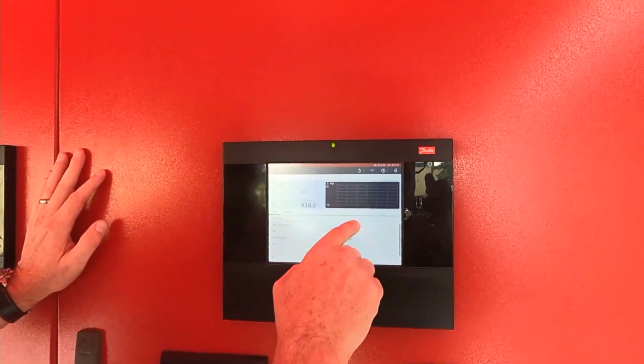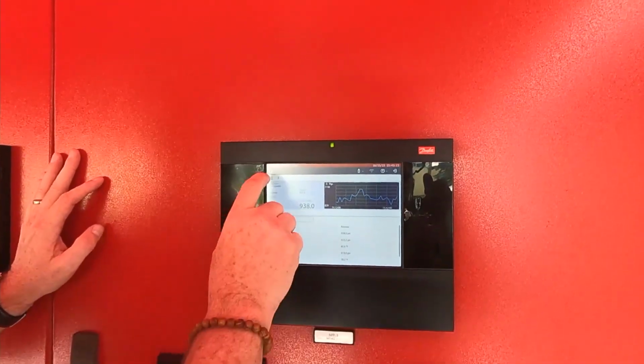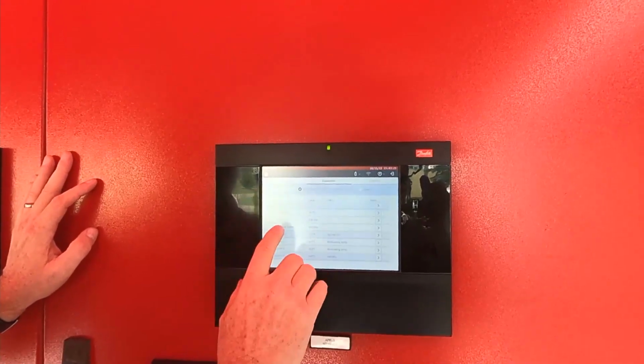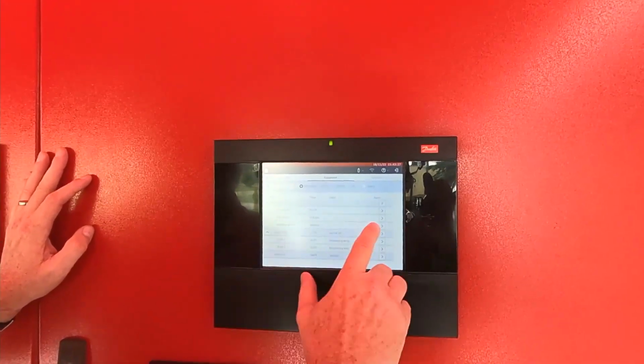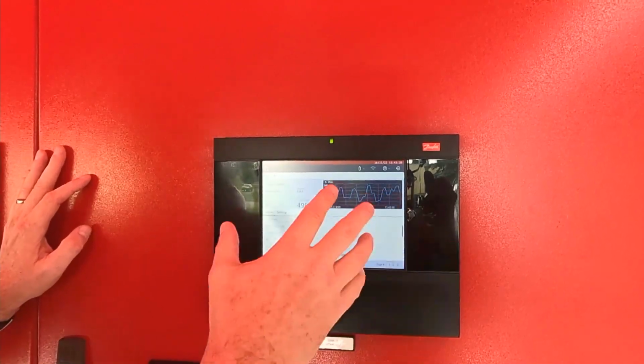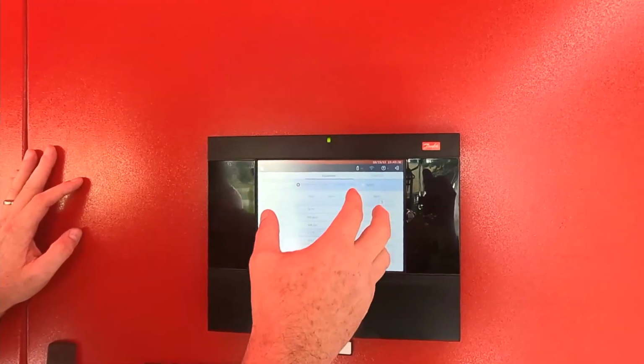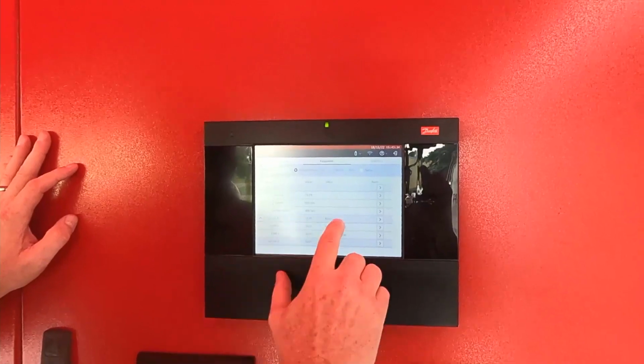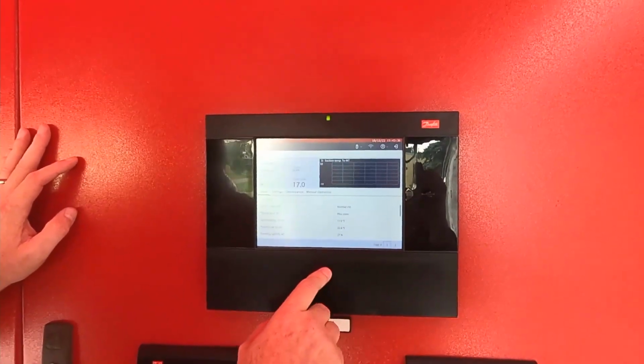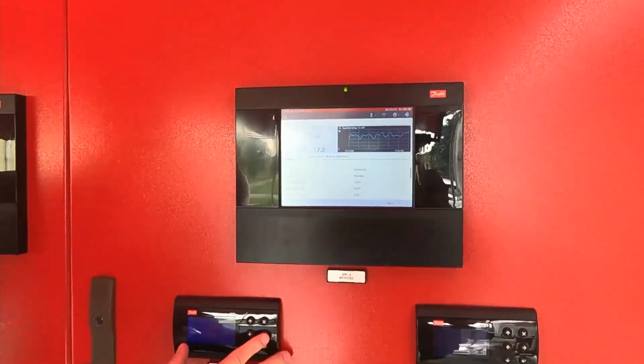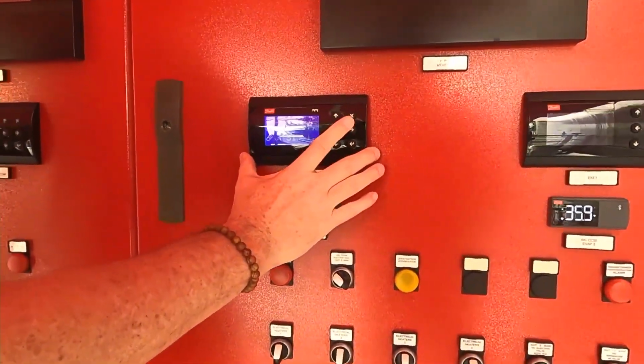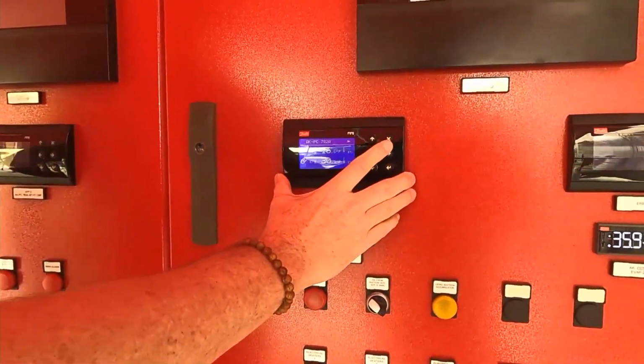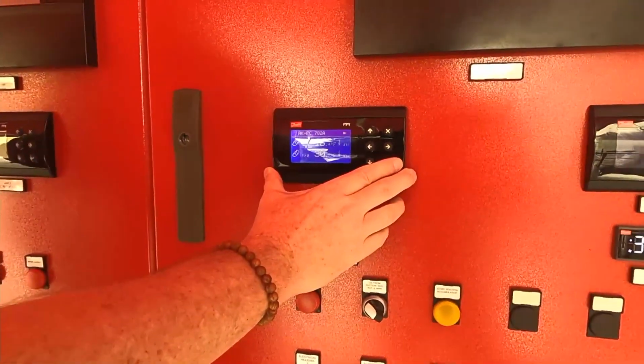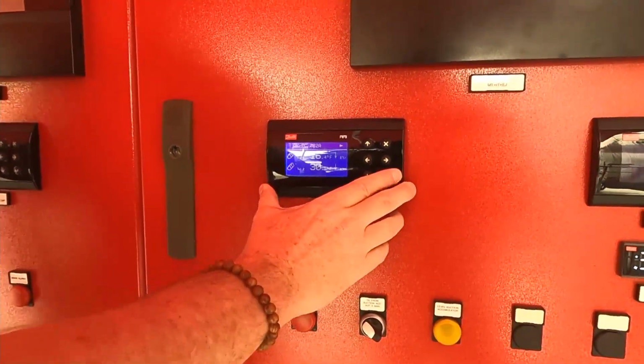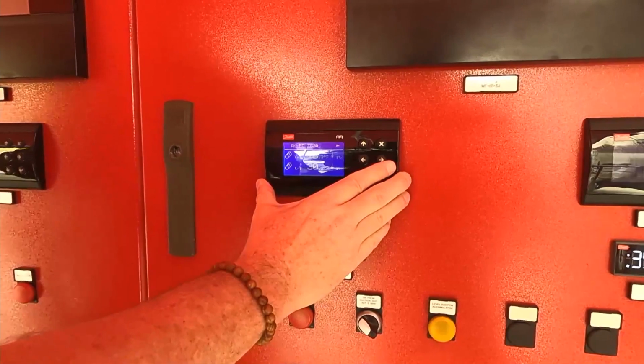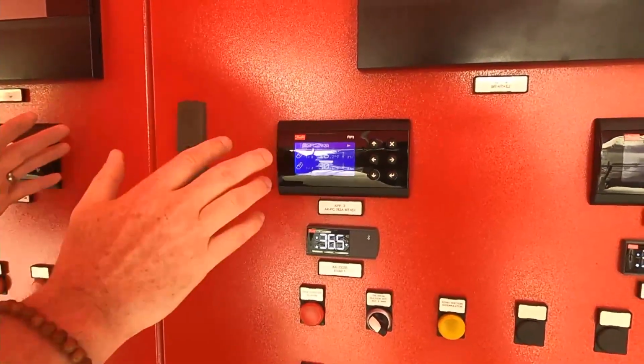So I can look here, see what it's doing. I can override the valve positions. I can do most of the things set point wise that I would need to do. This is our receiver control. So that functionality is already in the SM800. We've got our medium temp compressor shown here. There is also for the pack controller, if we come down one, there's also a remote display. We have a wonderful, easy to remember model number of MMIGRS2 for some reason. But this remote display, it will let you see the I/O for the pack controller.